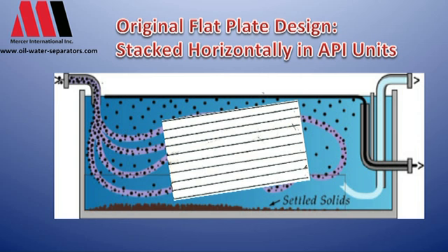And what this did was this allowed smaller droplets of oil to be removed out of the wastewater in the same size tank. And so instead of an API unit removing 150 microns, now you could have an API unit removing, say, a 100 micron droplet. And therefore you'd have a better effluent criteria on the way out. The effluent of the oil would be lower.